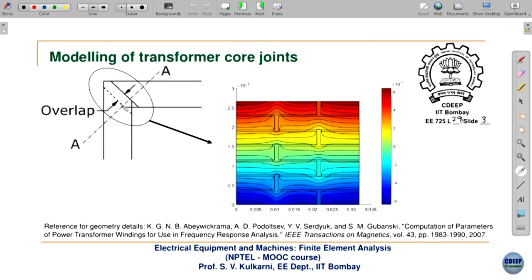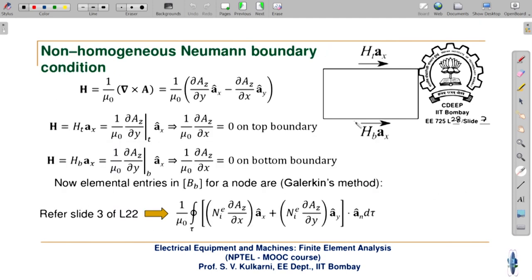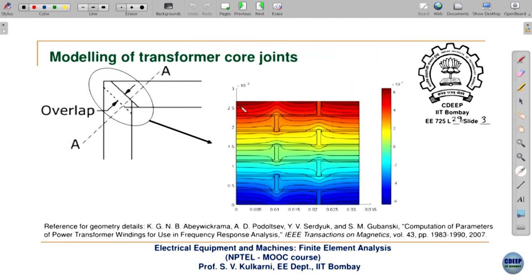The air gap here is alternating — it does not appear at the same place in successive layers. If the gaps appeared at the same position, the whole structure would be mechanically weak. So there is an interleaved joint design where the air gaps appear at different positions, making the entire joint mechanically stable. The geometry details are taken from the referenced paper.